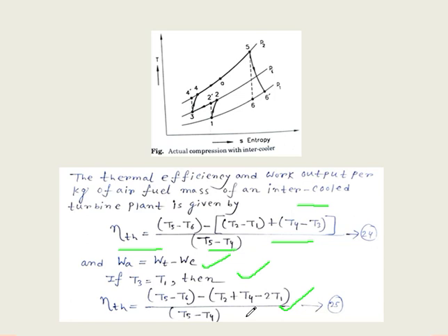The number of stages used for compression depends upon the overall pressure ratios of the plant. More than 2 stages with intercooler after every stage can be used for high pressure ratios. The number of stages used is generally decided as per the saving in the work done and extra capital required for the equipments used as compressors and intercoolers. Generally, only 2-stage compressor is used in gas turbine plants, as maximum pressure ratio is limited to 10 only.